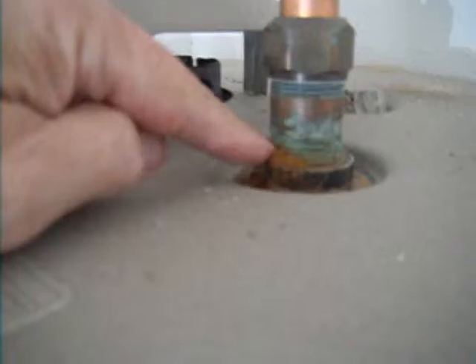Then we're going to look at the flue, make sure it's not loose — it is in place. And we're going to look at the pipes going into the actual water heater itself, and you can see here we have rust.